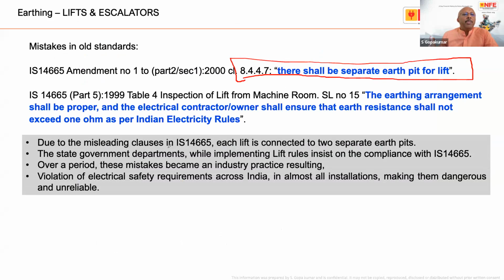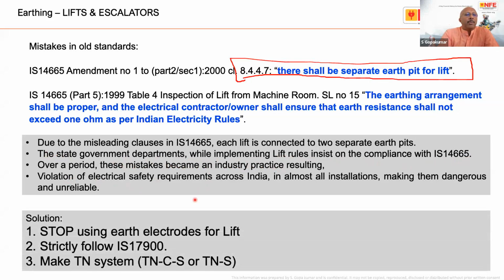It's a mistake. Due to the misleading clauses in the old standard, each lift is connected to a separate earth pit. Practically, this is what is happening in most places. The state government departments, while implementing lift rules, insist on compliance as per this particular standard. As a result, over a period of time, these mistakes have become an industry practice, resulting in violation of electrical safety requirements across India in almost all installations, making them dangerous and unreliable. Why unreliable? Because in case of any fault on the HT side of the transformer, the transferred potential will kill your electronics. So as Mr. Nitin told, we should stop using a separate earth electrode for the lift and strictly follow IS 17900, making the TN system either TN-C-S or a TN-S system.